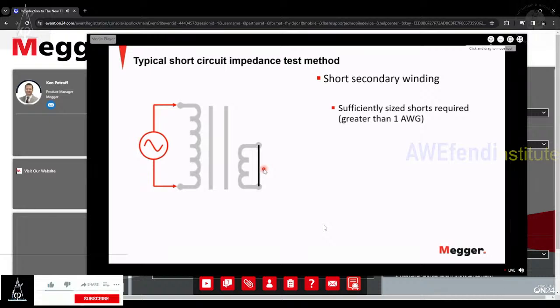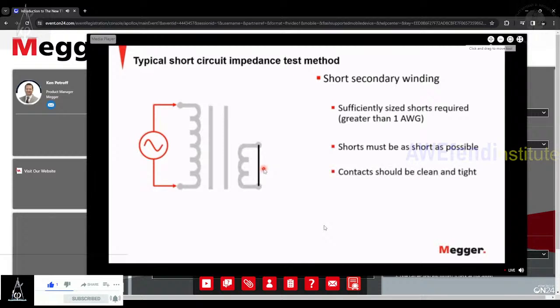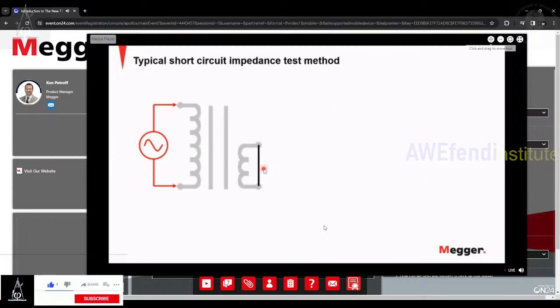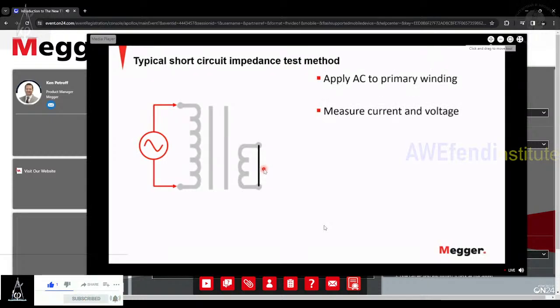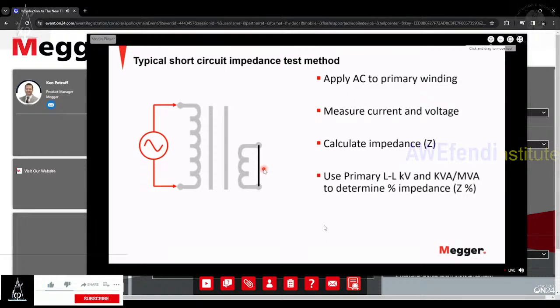So you have to make sure that it's sufficiently sized, clamped on there, screwed down with nuts and bolts. You want to make sure that the shorts are as short as possible. Those contacts, again, not only secured on there tightly, but clean and tight. You then apply AC to the primary winding. You measure the current and voltage to calculate the impedance. And then you use the primary line-to-line voltage, the kVA, MVA, to determine that percent impedance value based on the measurement. And from there, you can then compare it to the nameplate value, and it needs to be within 3% to be considered within the limits.